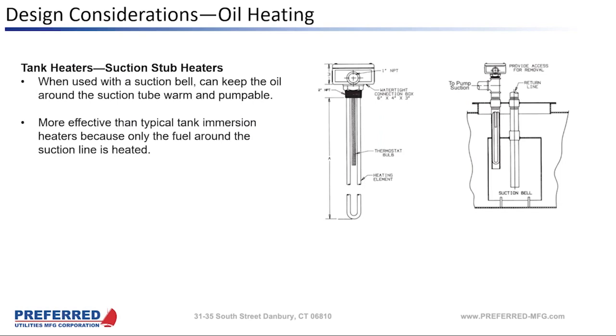So this is a very old school trick called a stub heater. The stub heater is either an electric heater or a steam coil heater that just heats up the oil around your suction pipe in a main oil tank. Because the idea there is you don't need to keep all of the oil warm, you just need to keep the oil warm that you're going to pump. So it cuts down on the kW that you consume or the steam you consume and just keeps some of the oil warm. And it's more effective than typical immersion heaters because it's not trying to heat the oil in the whole tank, just the oil that you're concerned with, the oil you're pumping out of the tank. We still supply these. This is a 50, 60-year-old method that we still use once in a while.